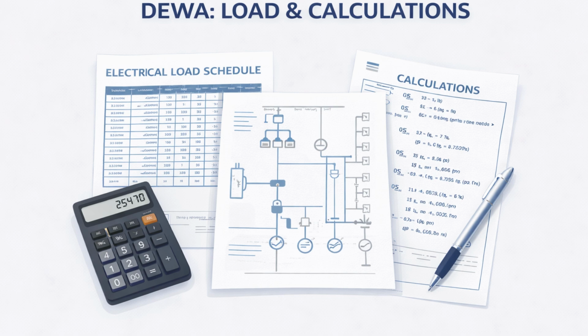Now let's talk about major hold points. The most common reason for DEWA rejection is mismatch. Mismatch between drawings and authority forms, mismatch between load schedules and SLDs, mismatch between calculations and reported values. Another major issue is load changes after approval. Once DEWA approves your loads, they expect those numbers to remain stable. Changing loads later means resubmission, additional approvals, and project delays. The third major hold point is inconsistent demand calculations. If your demand factor changes from one document to another, DEWA will immediately flag it. This is why DEWA expects discipline and consistency.